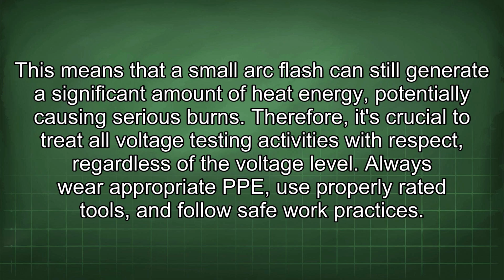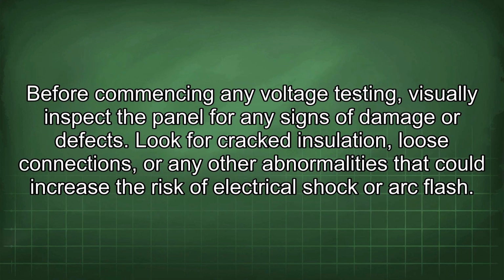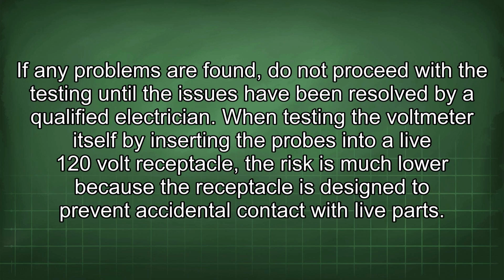Always wear appropriate PPE, use properly rated tools, and follow safe work practices. Before commencing any voltage testing, visually inspect the panel for any signs of damage or defects. Look for cracked insulation, loose connections, or any other abnormalities that could increase the risk of electrical shock or arc flash. If any problems are found, do not proceed with the testing until the issues have been resolved by a qualified electrician.